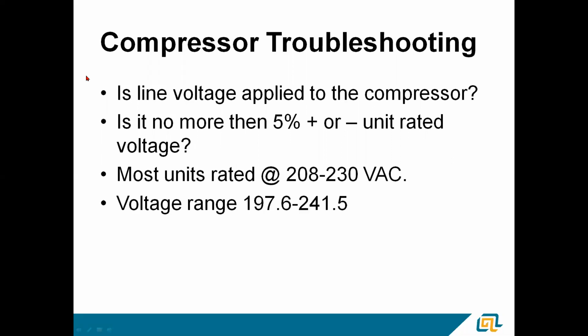So now we want to check, do we have our line voltage applied to the compressor? It shouldn't be anything more than 5% plus or minus the unit rated voltage. Most of our units, scroll compressors, are rated at 208 to 230 volts. So the range, when we factor in that 5% plus and minus, is 197 to 241 volts. And I just heard everybody say, wait a minute, 240 volts is very common. I've never felt this apply so much on the high end. If we're running a little higher voltage, 247, 248, the compressor's still going to run, shouldn't be any motor damage.